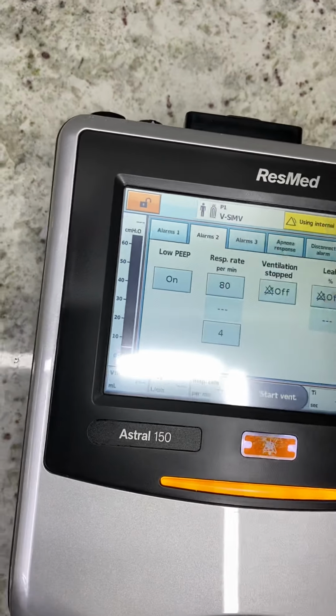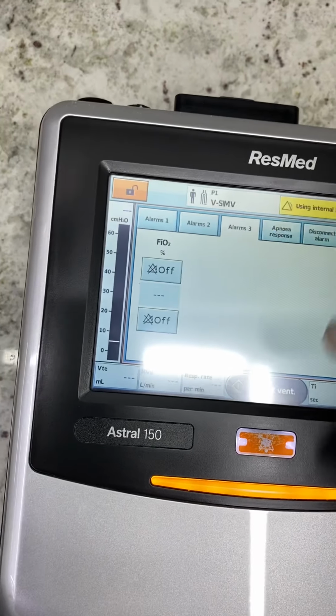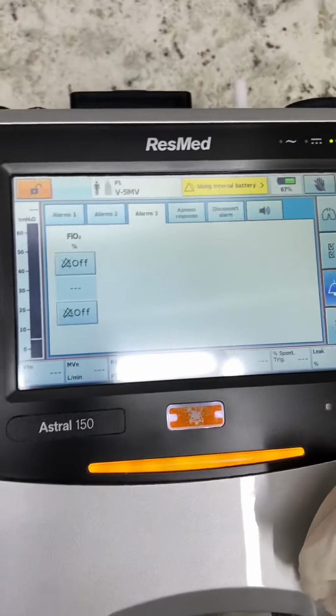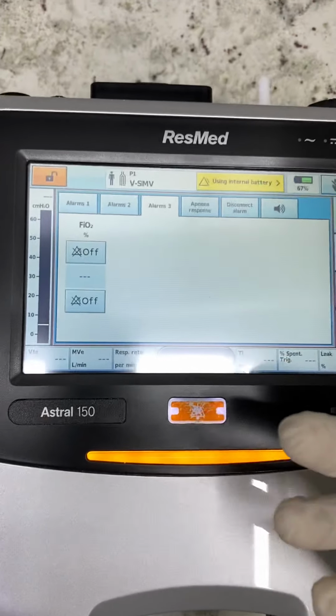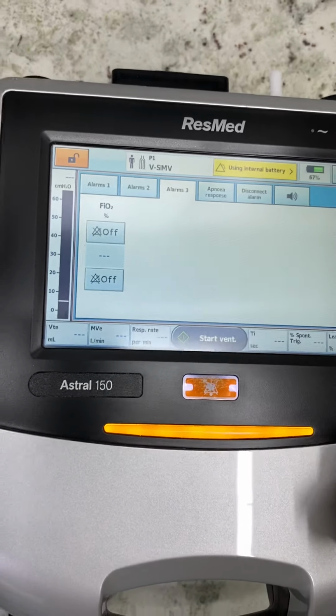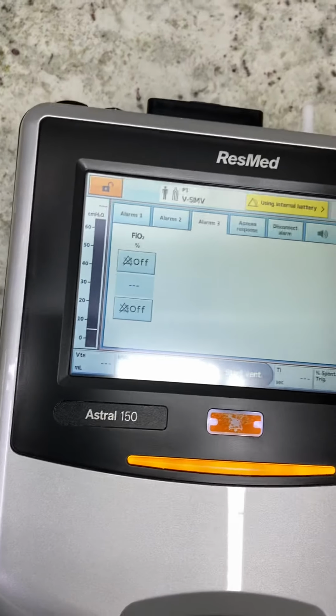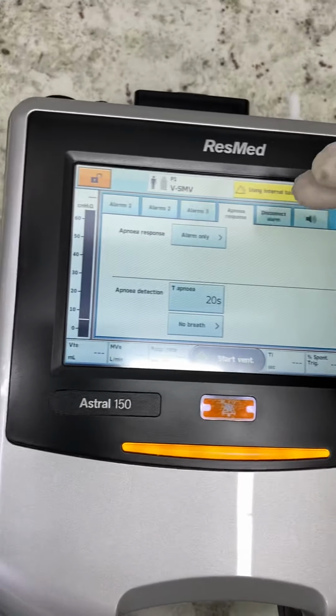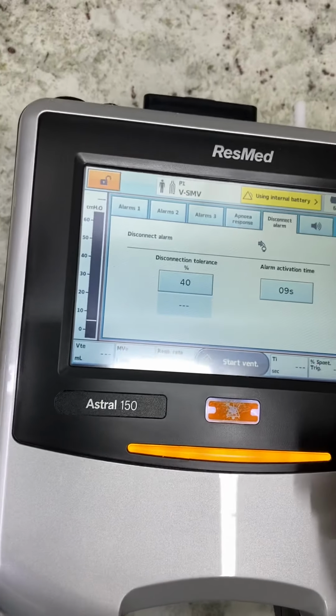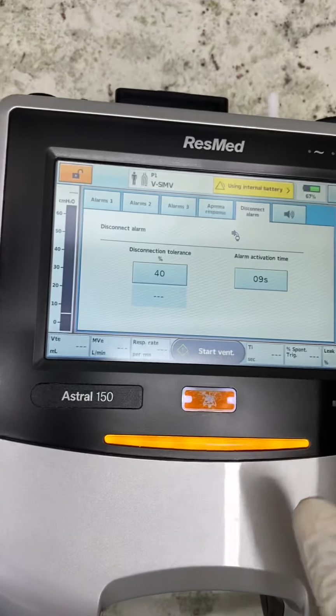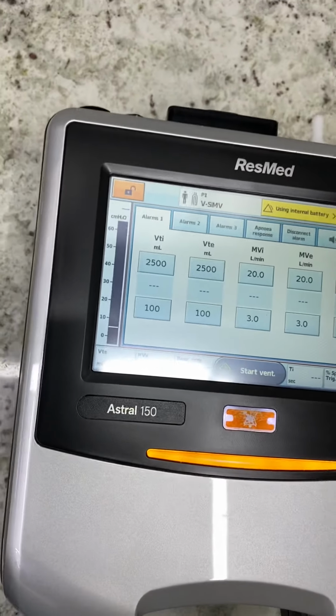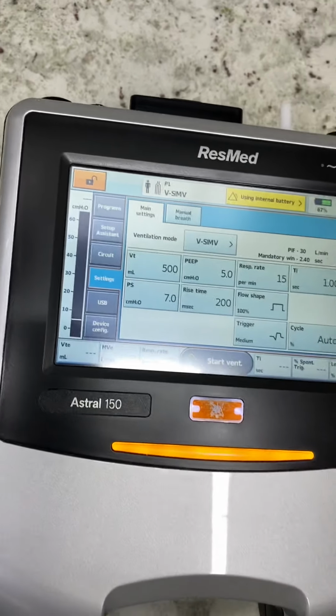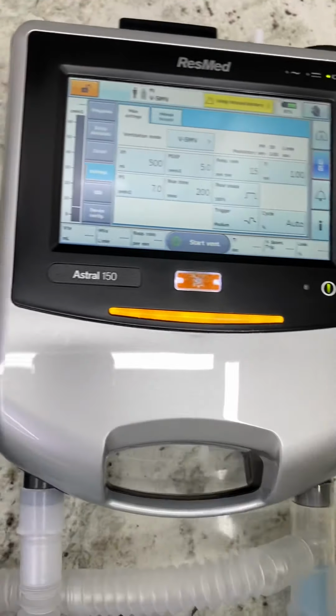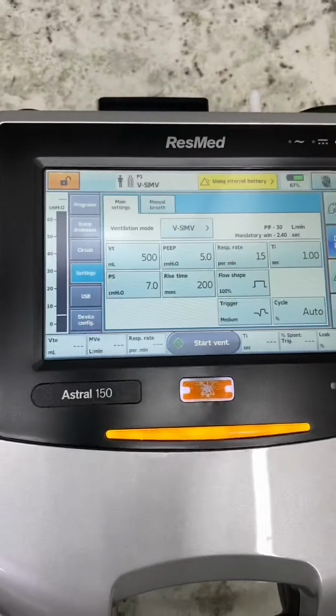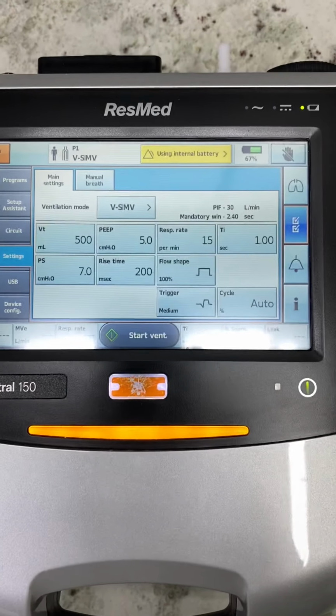Everything, alarm 2, everything. You can turn off some unwanted alarms. FiO2, if you don't want to monitor the FiO2, because it's not mandatory. The oxygen is just monitoring, it's not controlling any oxygen supply to the patient. You can turn it off, or if you want, you can keep it. Apnea response, disconnection alarm, how much percent you want. Some of them come default, but you can set them up by yourself. Then that's it. Once you set up everything, you can start the ventilation. You can connect the patient and start the ventilation. Just I will hold on with the next video.